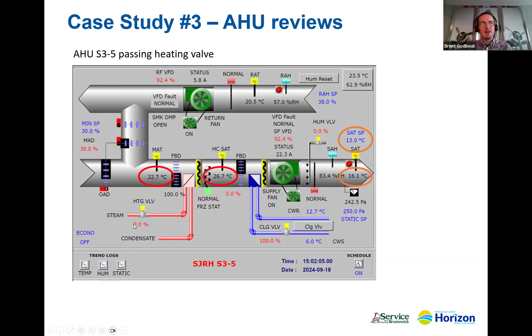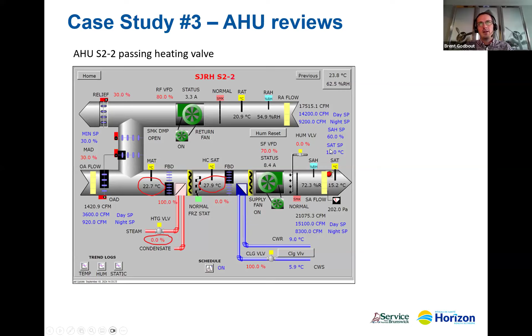Also found a second one, same situation. This was another air handling unit, and the same thing going on. We're picking up a little bit more temperature in this case. Still indicating that the valve should be closed on the heating side of things, but the cooling valve is screaming at 100, trying to meet our set point, which we're not doing.